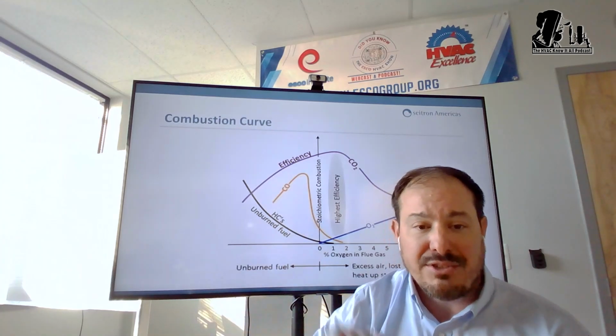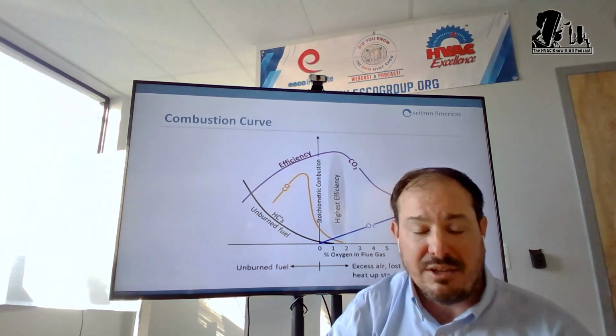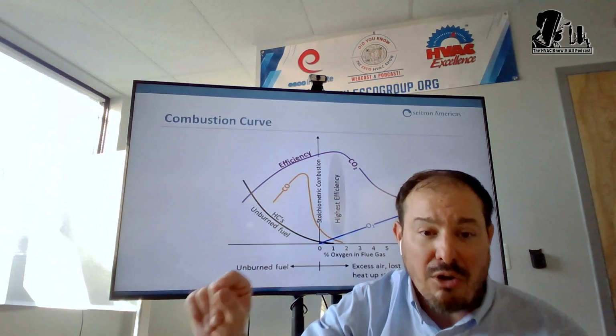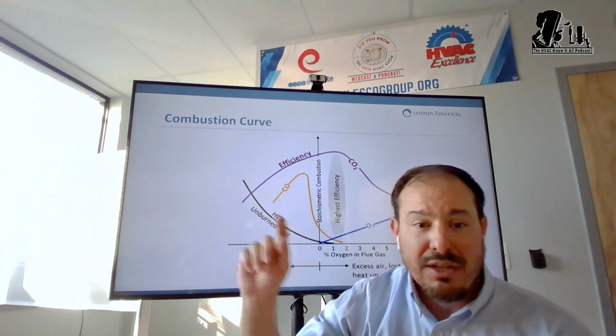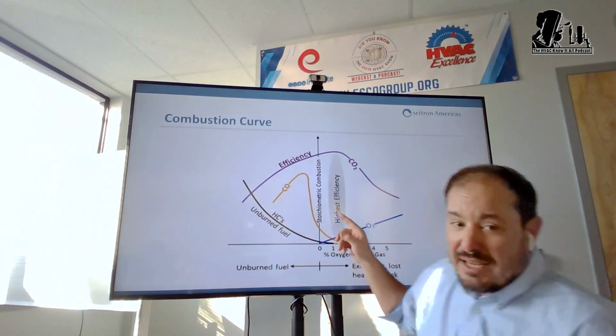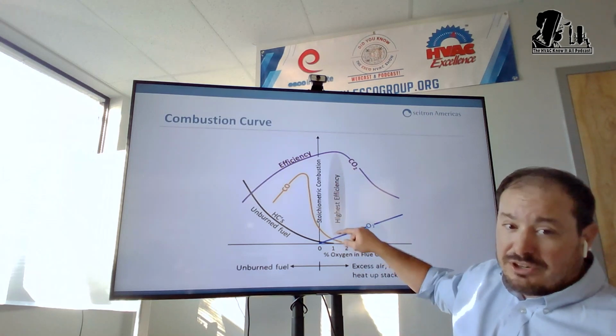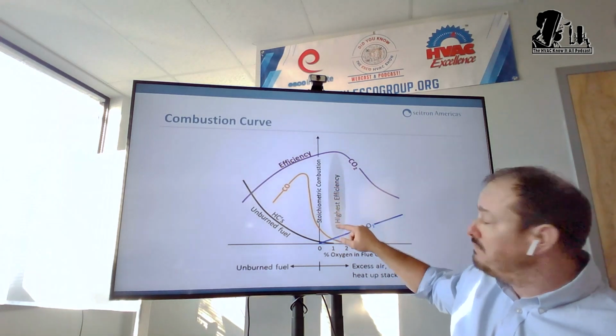What a manufacturer does in that installation manual when he says, okay, on high fire, on low fire, on this and that, I want to see between this number and this number for oxygen, or this number and this number for CO2, or I want to be below 100 ppm on CO. The reason being is, you see this shaded area in the stoichiometric curve? It's on the air-rich side, right? So we're talking, for the guys driving in their truck, about the right side of the curve, which is the air-rich side. That's the good combustion side, right?